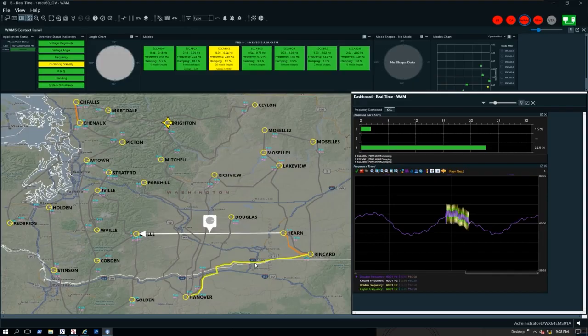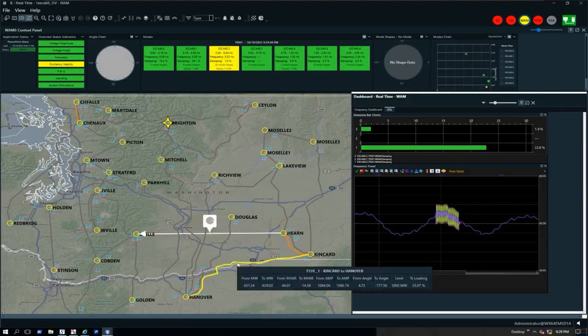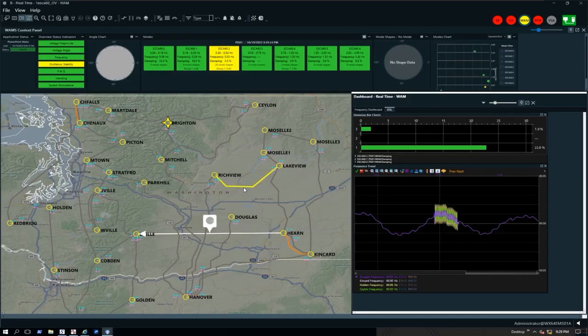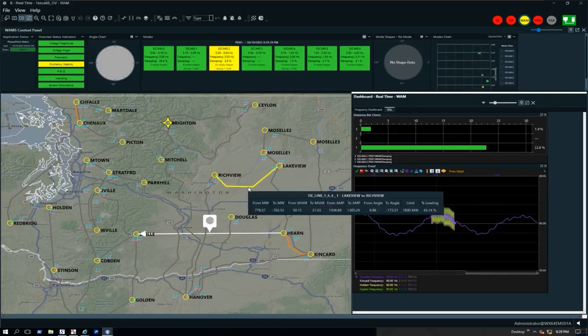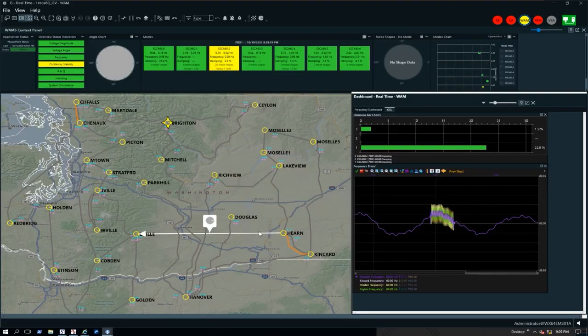resynchronization. So what I have in this is our ESCA 60 bus, if you haven't seen this before. So this model is a fictional 60 bus model based in the Pacific Northwest. And what I have here is essentially like a peninsula of generation and load in this transmission ring here. It's connected back to the system, there's two transmission lines that connect this ring of load and generation back to the transmission grid. So if I take these two transmission lines out of service, we'll see this smaller island separate from the larger electrical grid.